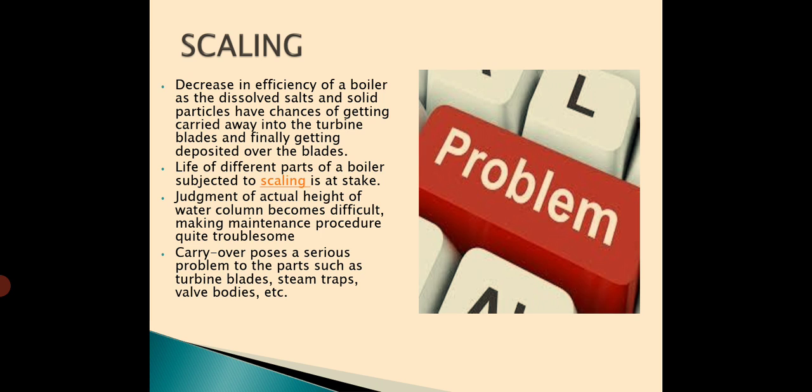Now, what are the problems caused due to scale formation or scaling? This scaling decreases the efficiency of a boiler as the dissolved salts and solid particles have chances of getting carried away into the turbine blades and finally getting deposited over the blades. The lifetime of the different parts of the boiler subjected to scaling is at stake. Judgment of actual height of the water column also becomes difficult making maintenance procedure quite troublesome, and carry over poses a serious problem to parts such as the turbine blades, steam traps, and valve bodies. These are some of the problems. Now, how to overcome these problems?